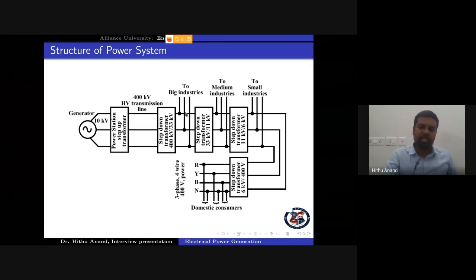We will discuss why we are distributing at 33 kV. The power is again stepped down from 33 kV to 11 kV and distributed to medium industries, and similarly stepped down to 6 kV for small industries. Finally, it comes to residential consumers, also called domestic consumers, where we step down 6 kV to 415 or 400 volt, three-phase four-wire supply, with three phases R, Y, B, and neutral.